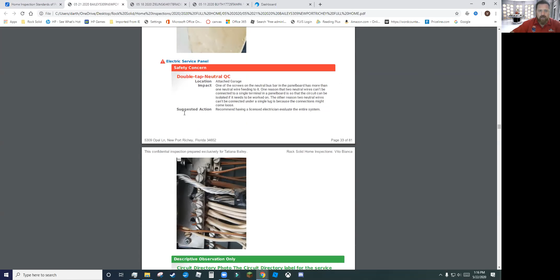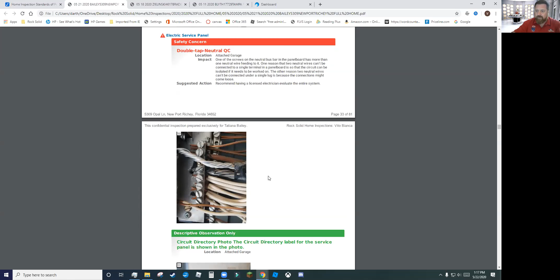Here we go, we have a deficiency right away - it was a double tap neutral. It's not a huge deal, and I know a lot of inspectors that don't call it out, but in this case I do, because if we're being technically honest, someone with a tester could read the whole thing as shut off when it's still live. So it does present a danger, and we call it out - I'd even call that out on a 4-point because it's a safety concern.